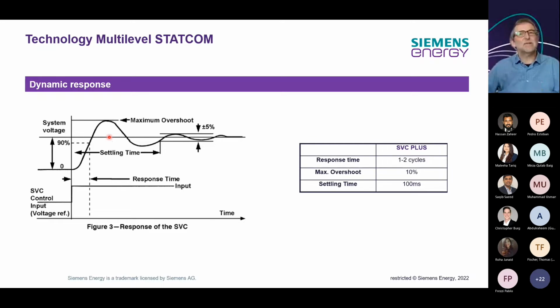But as this is depending on the grid, we do a measurement of the strength of the grid on a regular basis. Depending on the customer requirements, you do it every hour, every 2 hours, you measure the system strength, and then you will adapt the settings or the parameters in the control system to minimize the overshoot and to reduce the response time. Some typical values: the response time is 1 or 2 cycles, and we want to have the overshoot below 10%. And then there is a settling time, and you want to reduce this also, and we say after 100 milliseconds, the settling is done.